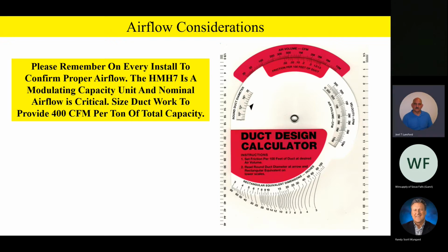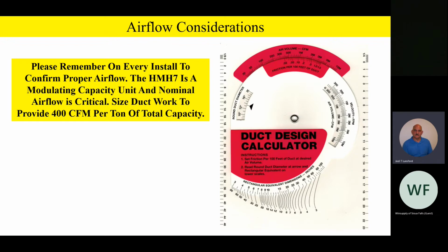So please remember, airflow is important on everything, but on a modulating system that's got these multiple sensors on there, airflow really becomes critical, that we provide that proper airflow, and we keep our coils clean, and we have a clean air filter, and all those important things that we should be doing anyway. But it really becomes important on a modulating unit, because it'll actually start reducing capacity if you've got a filthy filter. So just think about that a little bit as you start thinking about airflow considerations.